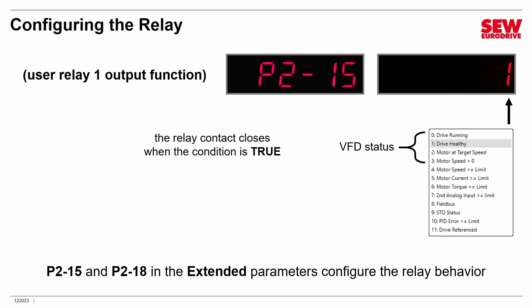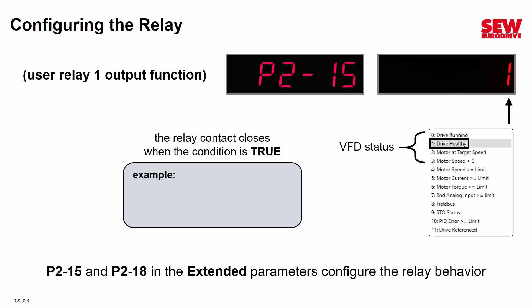The default option 1, drive healthy, indicates if the VFD is faulted or able to run. If the VFD is normal and able to operate, the relay contact closes signaling all is well. If the VFD goes into a fault condition, the relay contact opens to indicate this. This is a fail-safe arrangement — if something goes wrong like a power supply failure or a wire getting cut, it will signal back that something is wrong, rather than falsely indicating everything is fine.